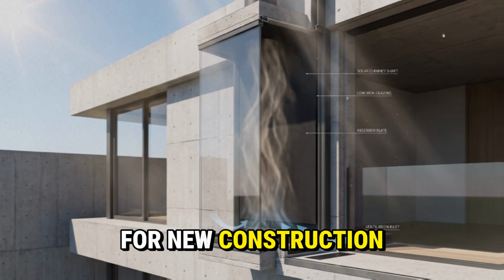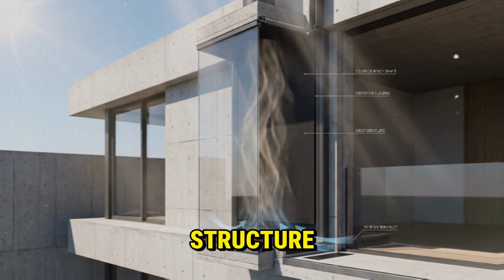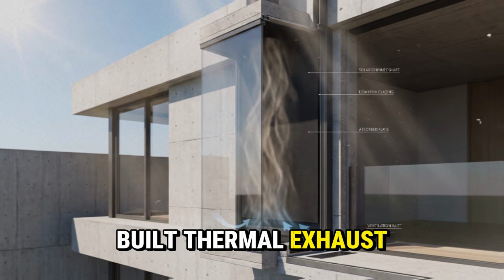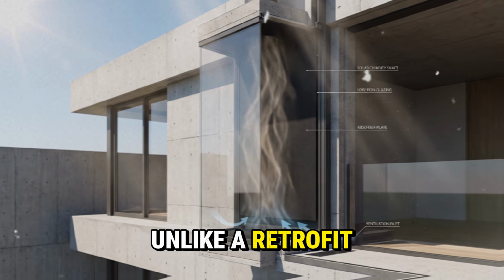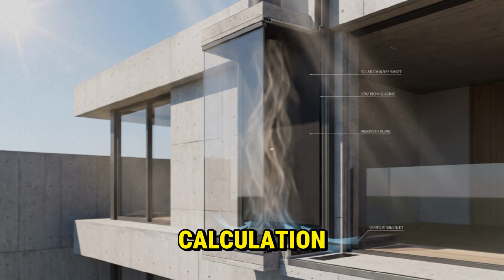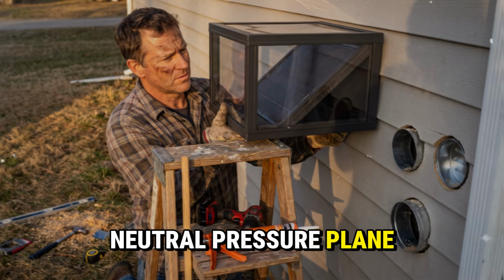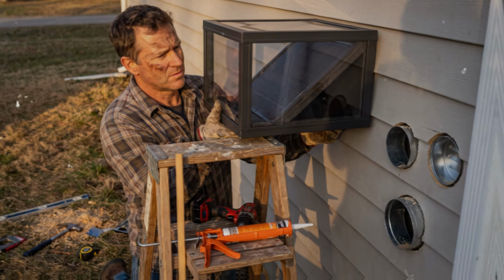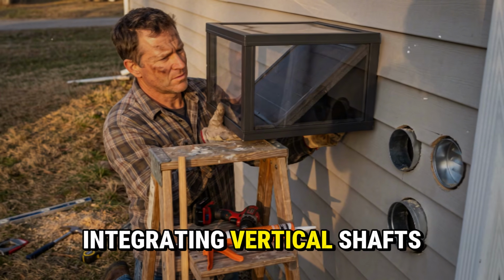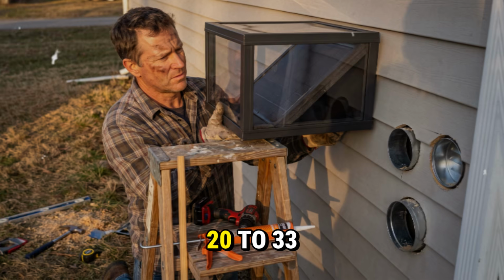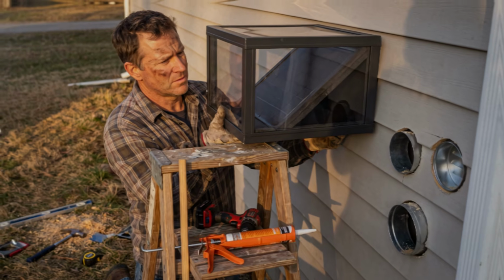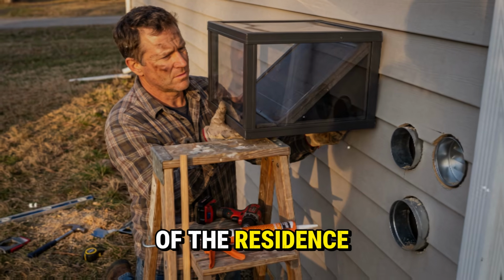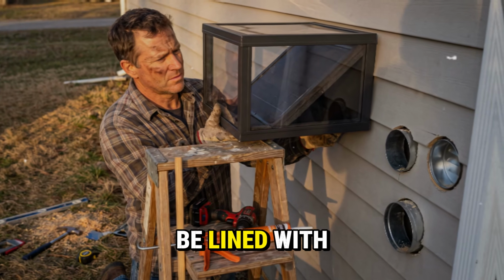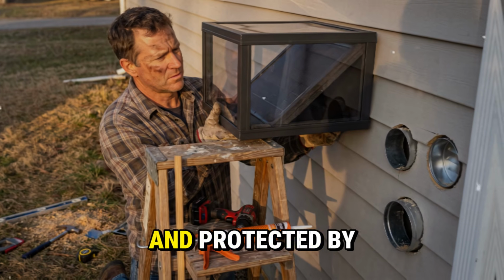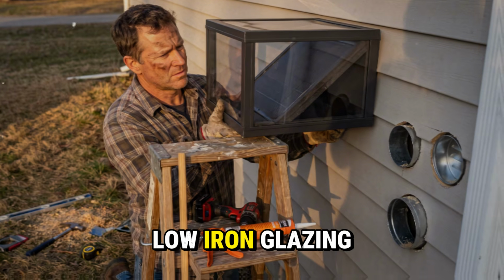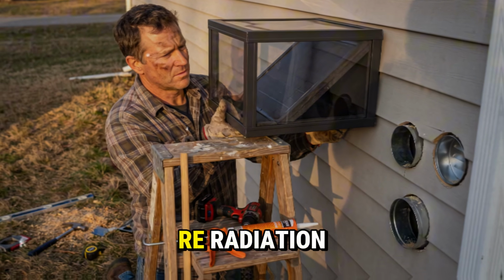For new construction, the optimal strategy involves designing the structure as a purpose-built thermal exhaust engine. Unlike a retrofit, a new build allows for precise calculation of the building's neutral pressure plane to maximize the stack effect. This strategy entails integrating vertical shafts, ideally ranging from 20 to 33 feet in height, into the south-facing thermal mass of the residence. These shafts must be lined with a spectrally selective absorber plate and protected by high transmittance, low iron glazing to prevent thermal re-radiation.